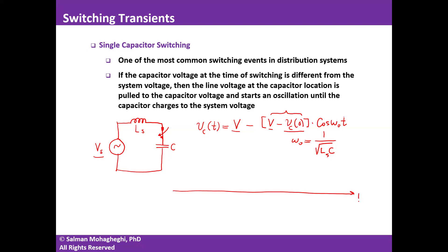Imagine my system has a sinusoidal waveform and the capacitor is connected at some moment in time with an initial voltage of zero. The system voltage would be pulled to the capacitor voltage and you will have an oscillation around that point until it damps out. This is an exaggerated version because the frequency is quite high, so on an oscilloscope you're probably going to see a bunch of spikes.